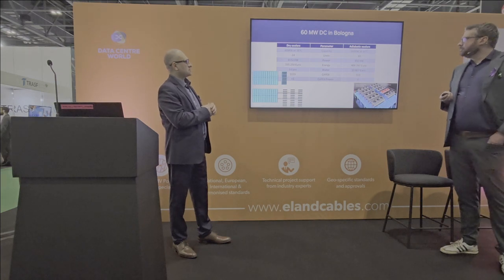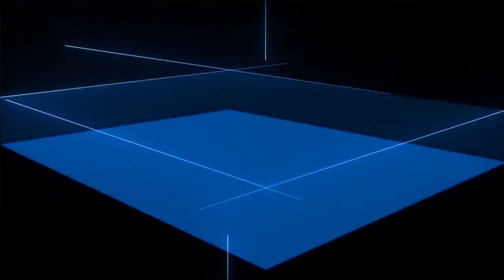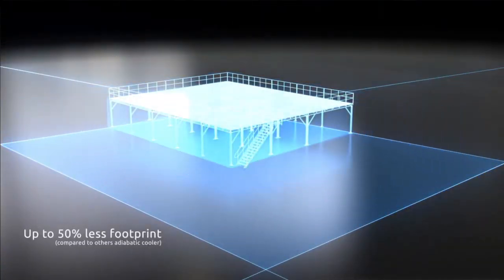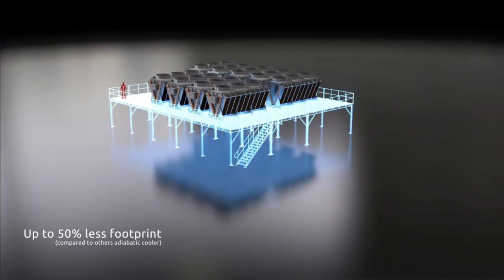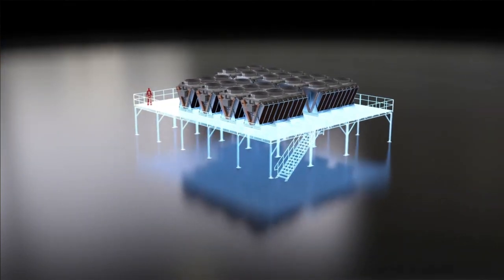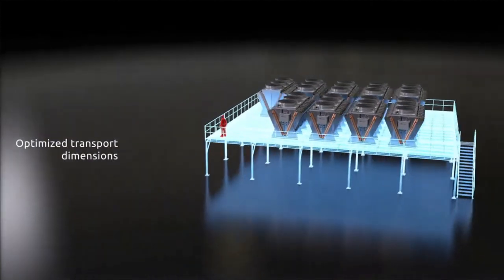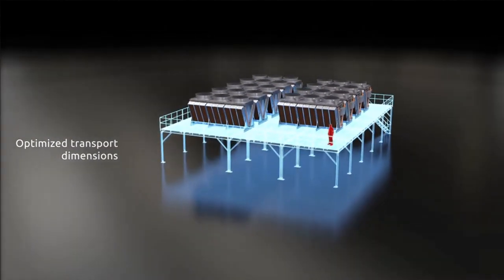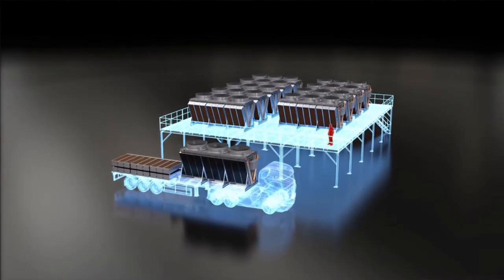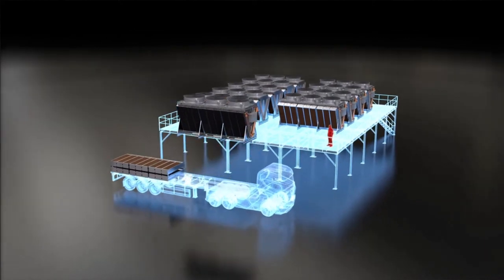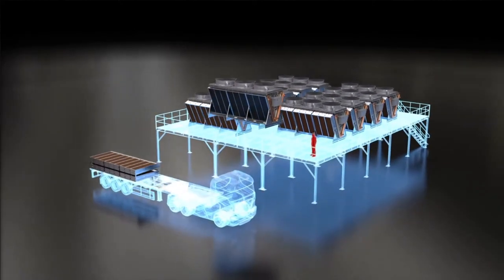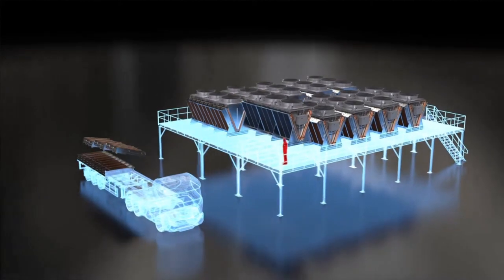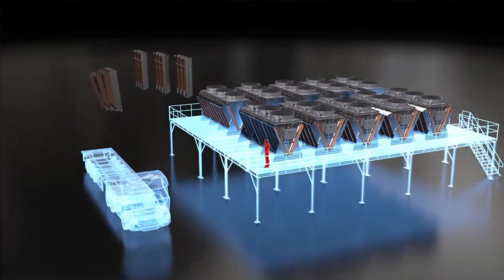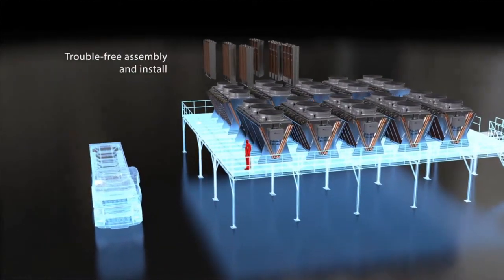And another approach is using adiabatic coolers, where we have only 10 adiabatic coolers and covering the same 48 megawatts, but the power input for the fans will be just half megawatt. So it's 3 times lower. And if we look for the cost of water usage during the year, it is just 13,000, 14,000 euros per year. So it's nothing.